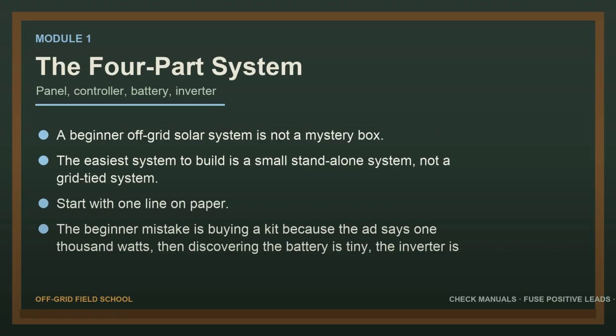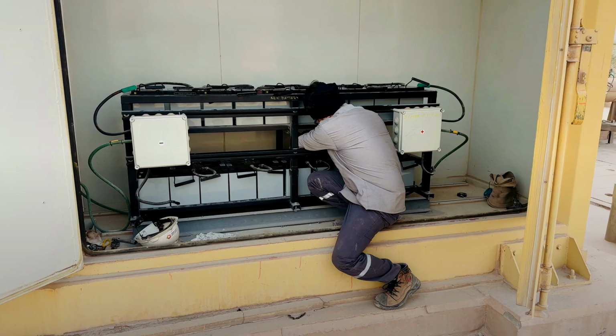Start with one line on paper. Panels go to a PV disconnect or breaker. That goes to the charge controller. The controller goes to the battery through a fuse. The battery goes to a main fuse, then to the inverter. DC loads can branch through their own fuse block.